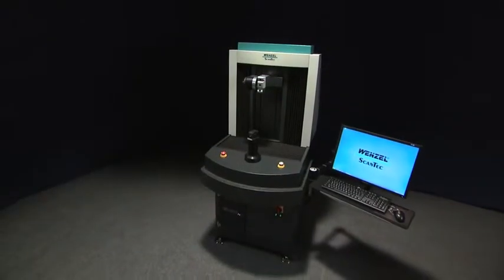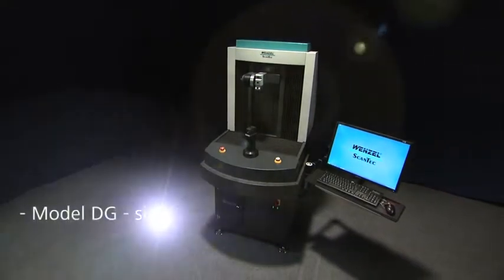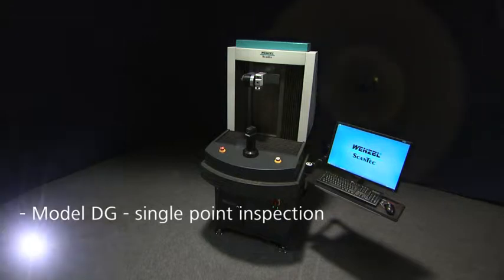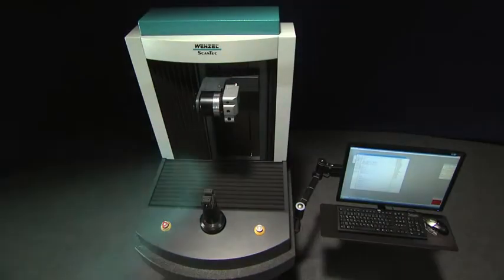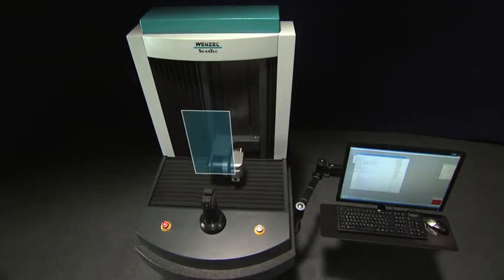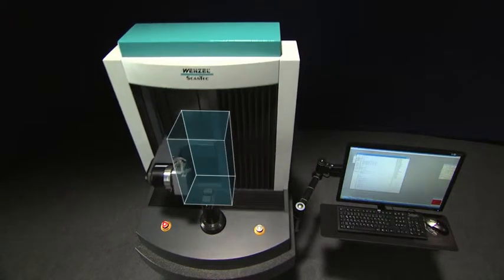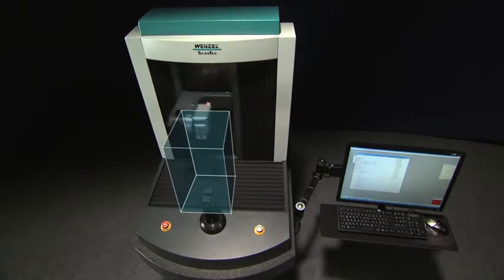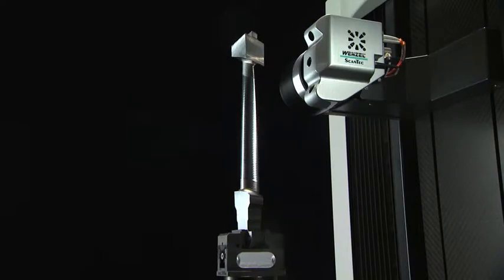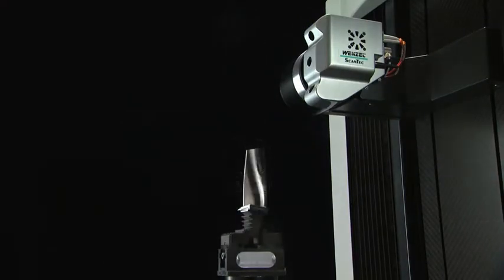CORE is available in two versions. The Model DG for single points inspection of parts and Model DS for part scanning combined with single point inspection. CORE has a travel range of 300 by 200 by 450 millimeters and has been optimized for the measurement of turbine blades, orthopedic implants and other small high volume quality critical parts.